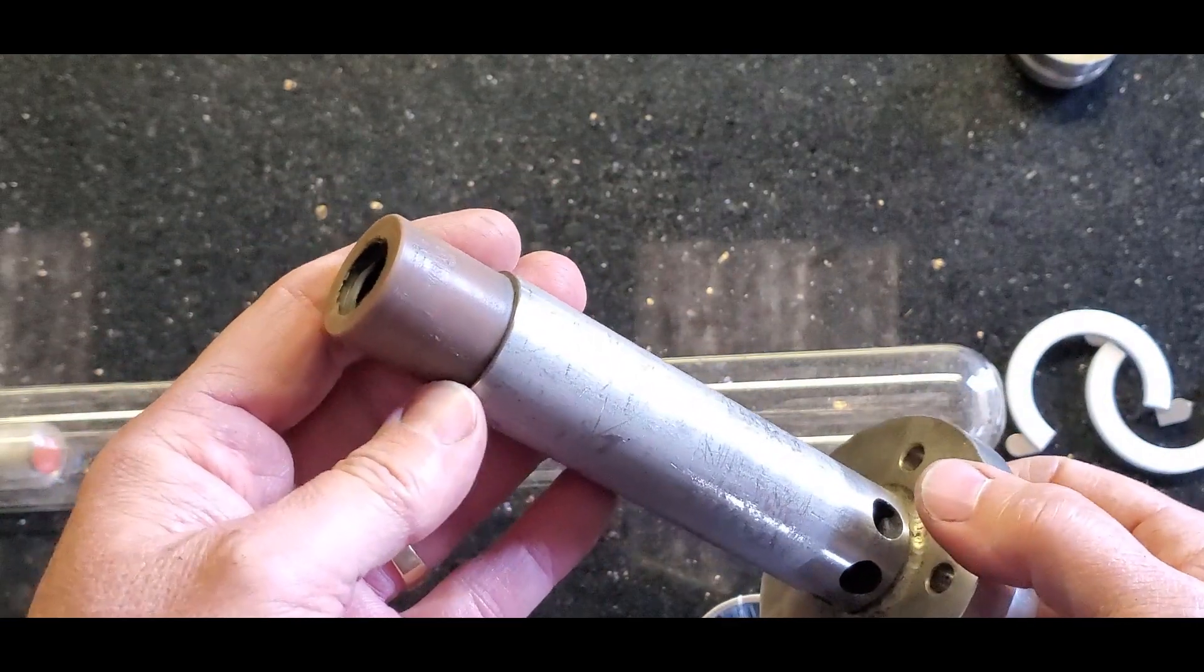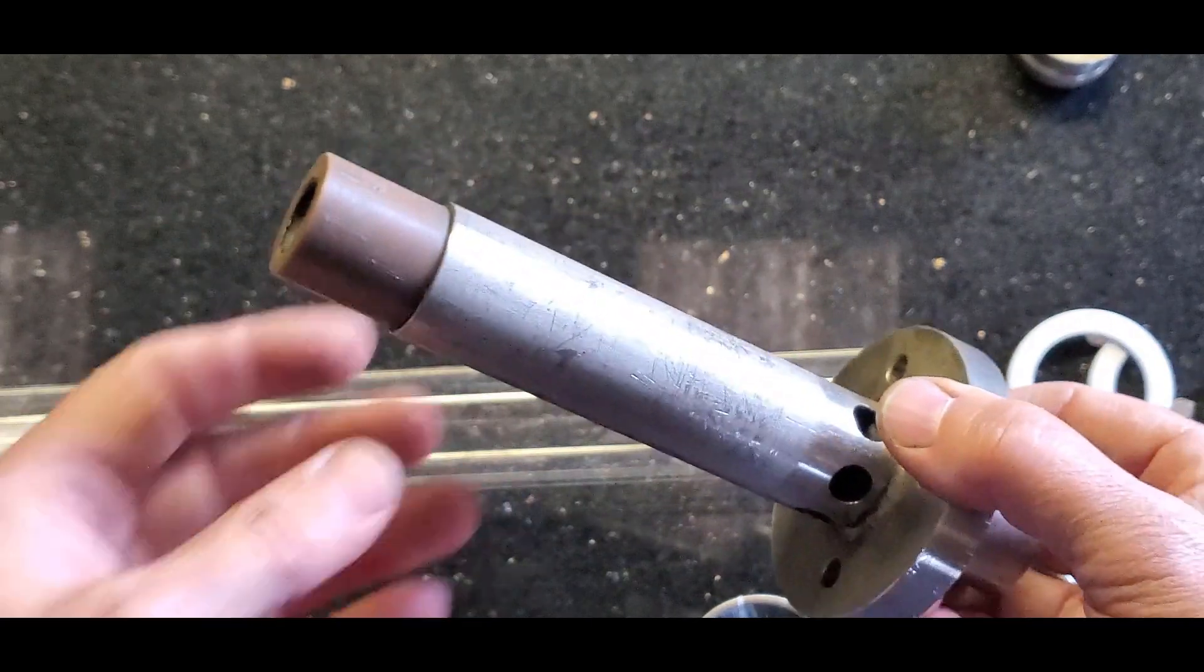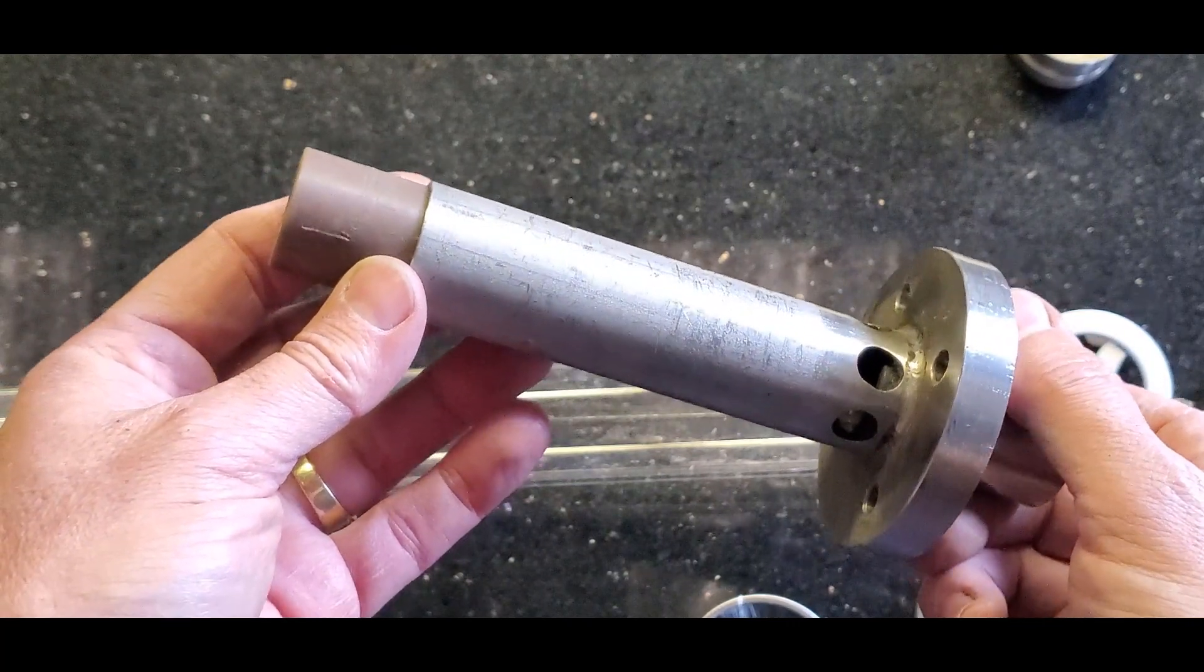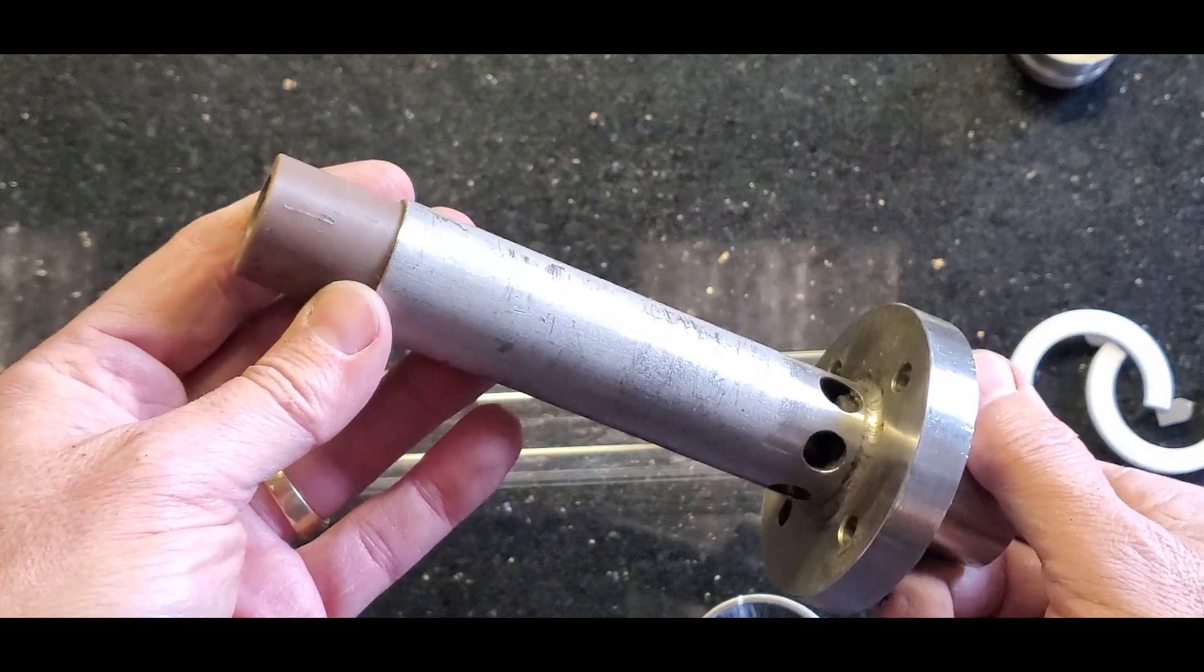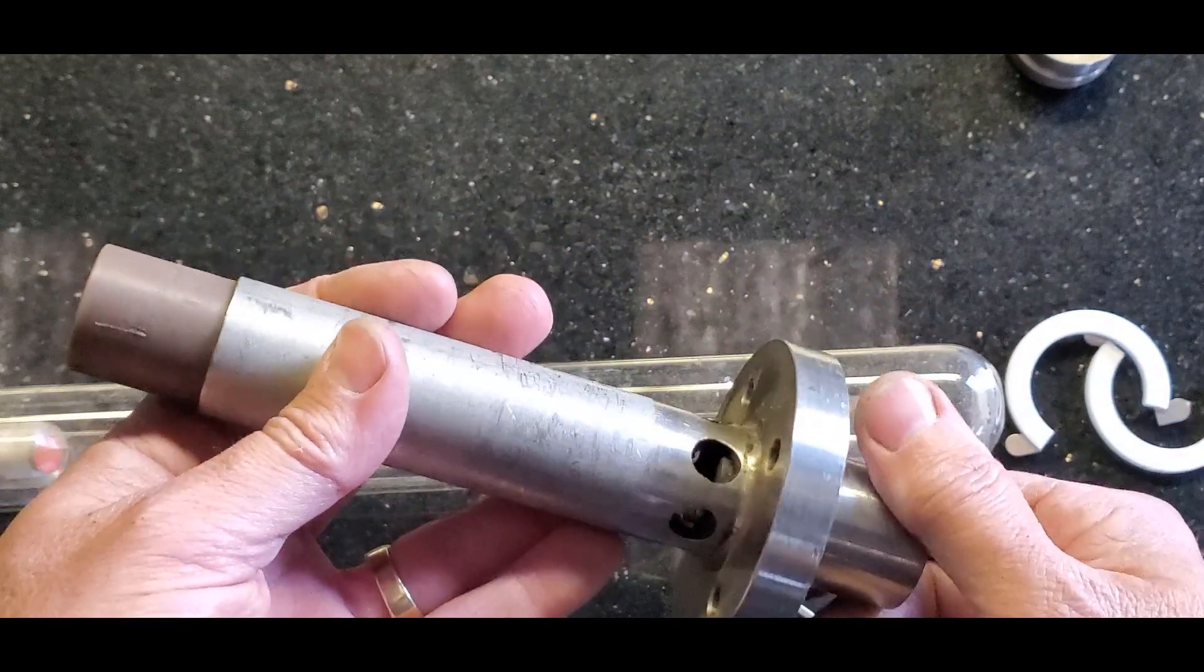I looked at this as two kind of separate problems. One was fairly easy in concept to fix. The Acme screw by the load table in the catalog was absolutely strong enough to carry a couple hundred pounds of load, but you can't push a six foot rod and expect it to stay straight. So I said that the Acme screw has to be in tension for both strokes. Now that's a problem because in order to put it in tension we have to have something on the bottom of the Acme screw which is at the bottom of the wastewater channel, like a thrust bearing. We had to tension the Acme screw with this thrust bearing in order for it to stay in tension and be able to drive the wiper plate back and forth without going into compression.